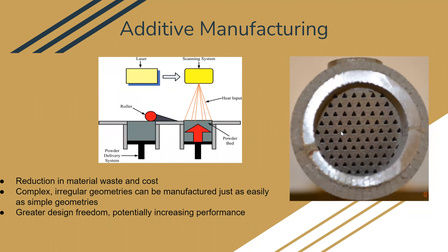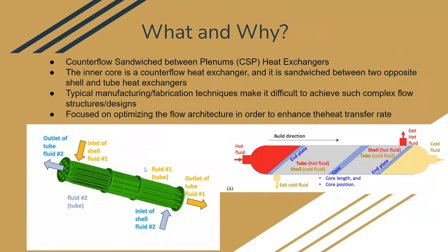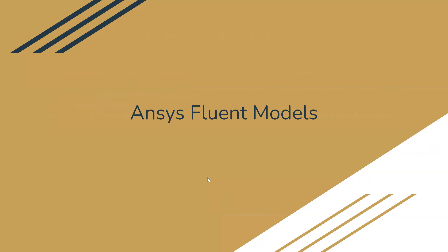This is illustrated here. It's the counter flow sandwiched between plenums, and it allows flow to go from the shell into the tubes, enabling a much more complex flow and optimizing heat transfer to be enhanced for more compact designs.